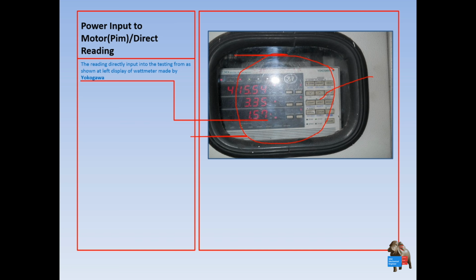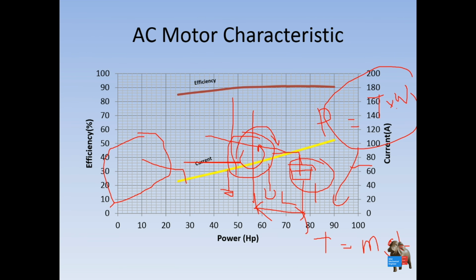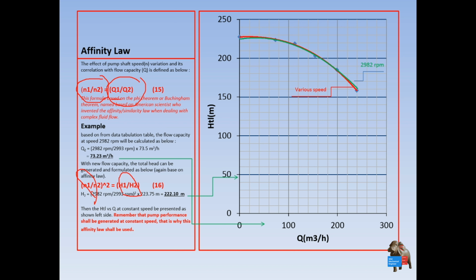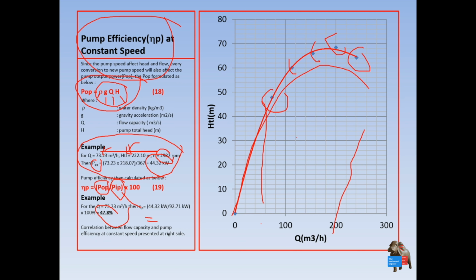So of course when you change the capacity, the motor speed will be different, and when you change it again to get more data, the motor speed can be different, but you need to represent the pump performance at the same motor rotational speed. That is why you need what we call the affinity law, as we discussed before. After you gather data, you have to convert all those rotational speeds to this single speed, and then from the single speed you determine the correlation to the head, the correlation to the flow capacity, and the correlation to the power input to the motor, and from that point you generate the pump performance chart.